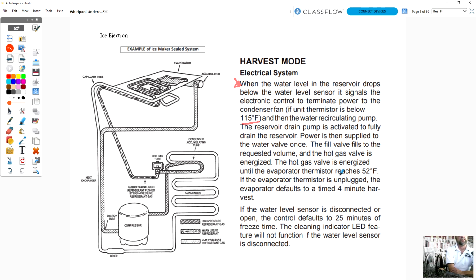And one of the reasons why they did it is if you heat water or refrigerate water, it tends to separate hard water deposits, calcium, lime, and iron, and other deposits and minerals that are in the water will separate from the water as the water freezes. And they're saying as the water flows over that slab of ice, it flushes those minerals back into your reservoir. Well, if we're not completely draining that reservoir out over a period of time, depending on whether the customer has really good water or well water in a poor, filtered environment, calcium and lime can build up all over the internal components of that machine.